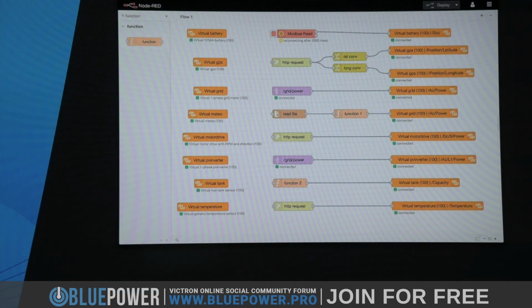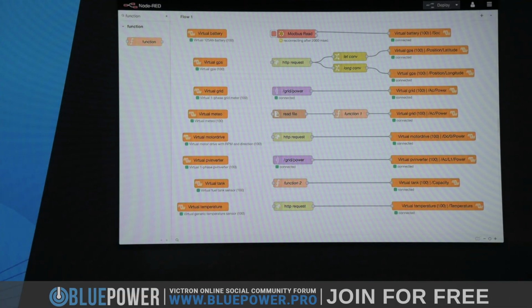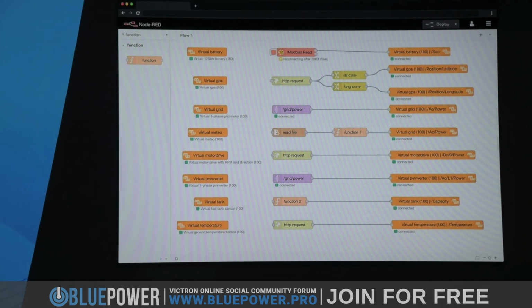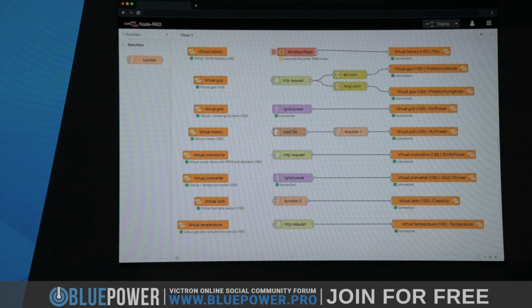Warwick, give us an example for a virtual battery. Let's say you've got a battery that doesn't have CAN communications, but it does have serial SMP or Modbus. Node-RED can speak to the battery using that other protocol, and then it can write the values to a virtual device in Node-RED. So it'll take the SoC value from Modbus or whatever and write it to the right parameter of the virtual device. So when you go to the device list in the GX, or on VRM, it will show a virtual battery with that SoC value.